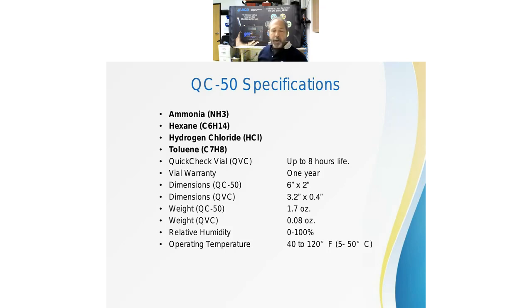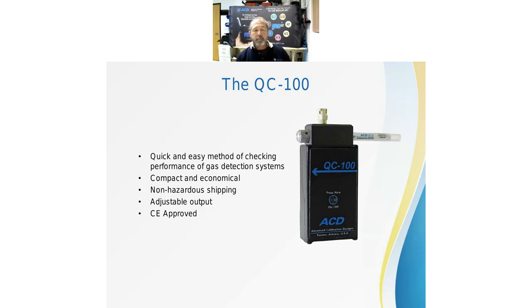These vials we rate for an 8-hour shift. So once you break that vial, we'll say you can bump test all the sensors you want for an 8-hour shift. Eventually, they do permeate out and evaporate, and then you don't get any more gas out of them. The next month or the next quarter or however, the next week, you break another vial and go around and bump test all your sensors again. And the QC100 is basically a motorized version of the QC50. So that knurled knob on the outside is a coarse adjust. You press the button, turn it on, there's an internal pump in this unit. And you walk up to your first sensor and open that coarse adjust knob until it alarms. And then you can walk from one to the next, and you don't have to keep squeezing the bulb.